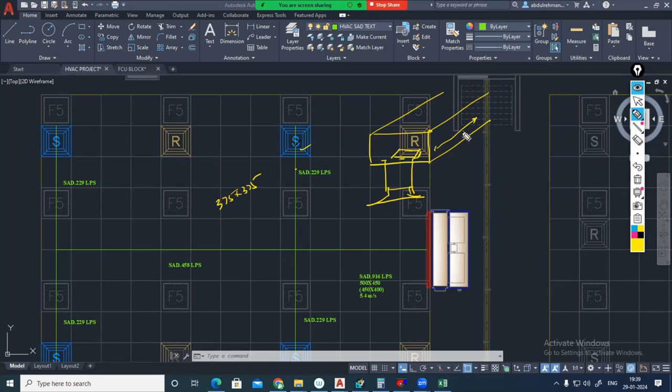So when you're considering from the top side, from the bottom side of the duct, I need to make a 375 by 375 hole. Actually 5 to 10 mm higher than that, I have to make the drop, but no problem. You don't want to mark that in the drawing. 375 by 375 minimum hole I have to make, no? So the duct has enough length there. That's why this side is not an issue. Here it is an issue.